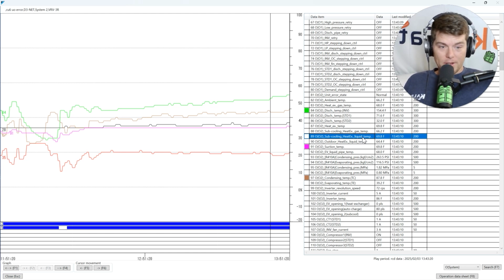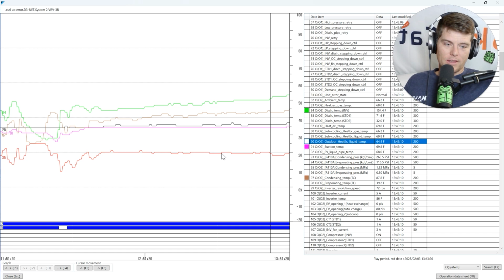Subcooling, it's gone up a little bit now. Okay, well, that's a little concerning. But we could also go back over to heat exchanger liquid temp. So, again, 2 hours of runtime data still is not enough data to troubleshoot this system. What would I do if someone sent me something like this? Okay, look at indoor pulses, right? Go through the rest of the system, and I would still tell you, this isn't enough data, guys, right? 2 hours is still not enough.